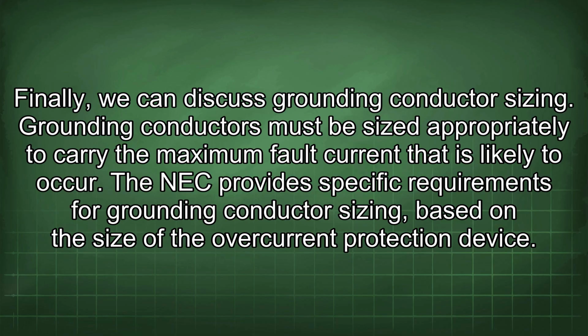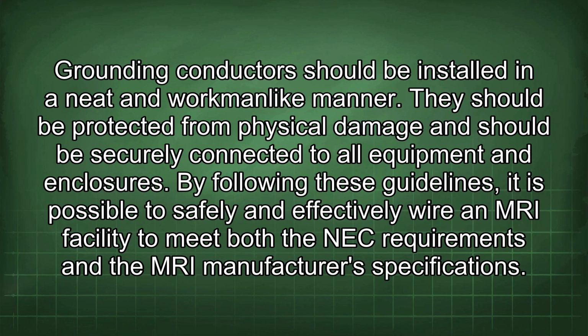Grounding conductors must be sized appropriately to carry the maximum fault current that is likely to occur. The NEC provides specific requirements for grounding conductor sizing based on the size of the overcurrent protection device. Grounding conductors should be installed in a neat and workmanlike manner. They should be protected from physical damage and should be securely connected to all equipment and enclosures. By following these guidelines, it is possible to safely and effectively wire an MRI facility to meet both the NEC requirements and the MRI manufacturer specifications.